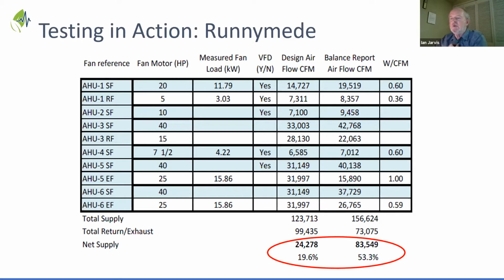The return exhaust, when you measured them and added them together, was a lot less than it should be. So the overall net supply, the pressurization of the building, was way higher than it should be. Again, at an excessive utility cost and significant effects in terms of comfort around all doors and exits and areas which were connected directly to the outside.